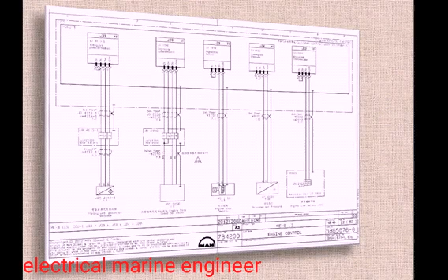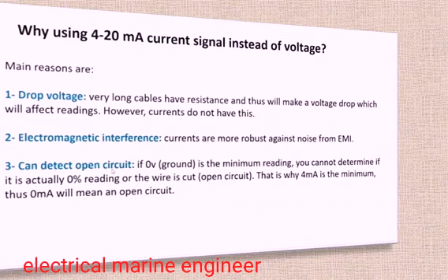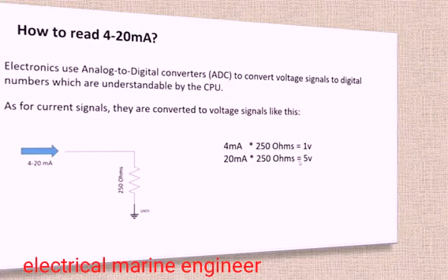And see, the reason is that if you transfer the signal by current, there is no voltage drop and no electromagnetic interference, and any open circuit can easily be detected. Because the current's minimum reading is 0, if you used 0 to 20 milliamps, then 0 would also represent an open circuit, so it would get confused. So for that purpose we are using 4 to 20 milliamps. And one more reason: the current signal can easily be converted into a digital voltage, which is easily readable by the computer. I showed you the circuit: they give 250 ohms, so that 4 milliamps gives 1 volt and 20 milliamps gives a 5 volt drop, which is easily readable by the computer. That is why we are using this.